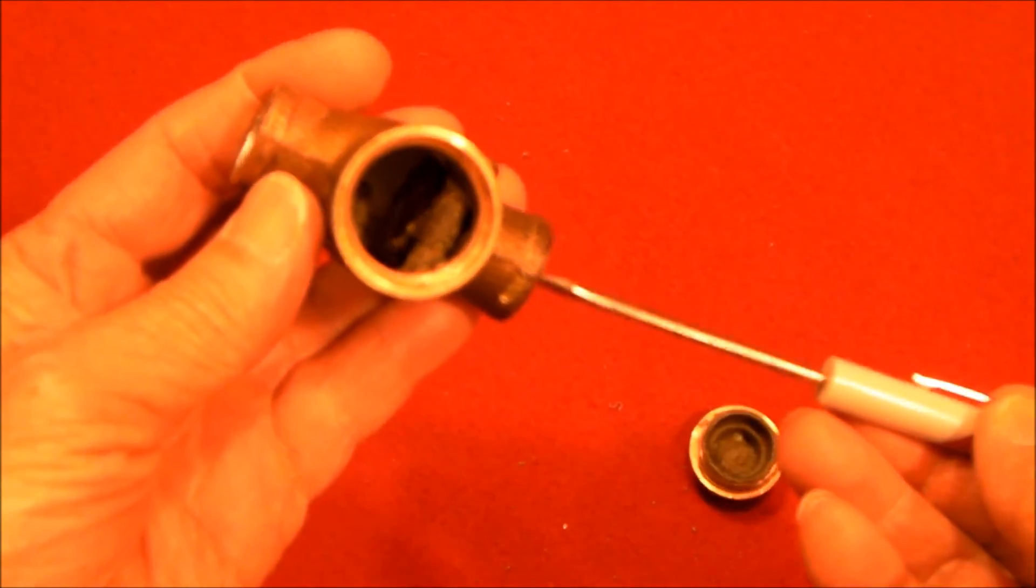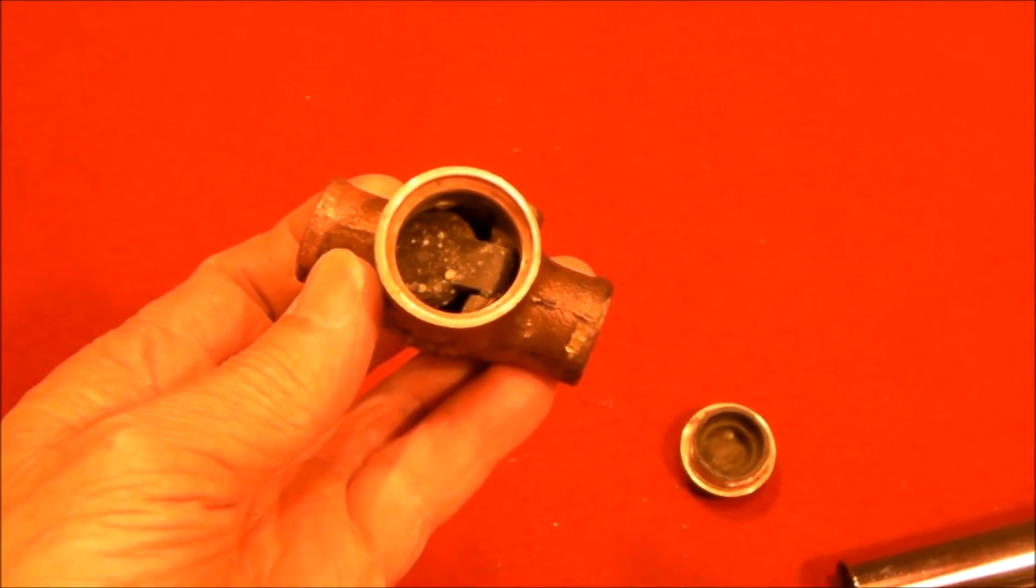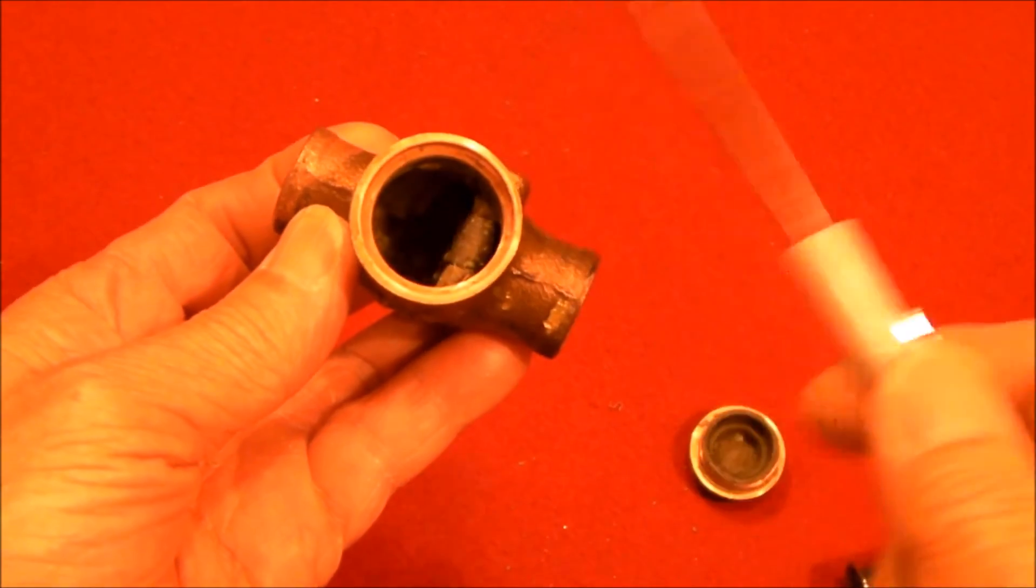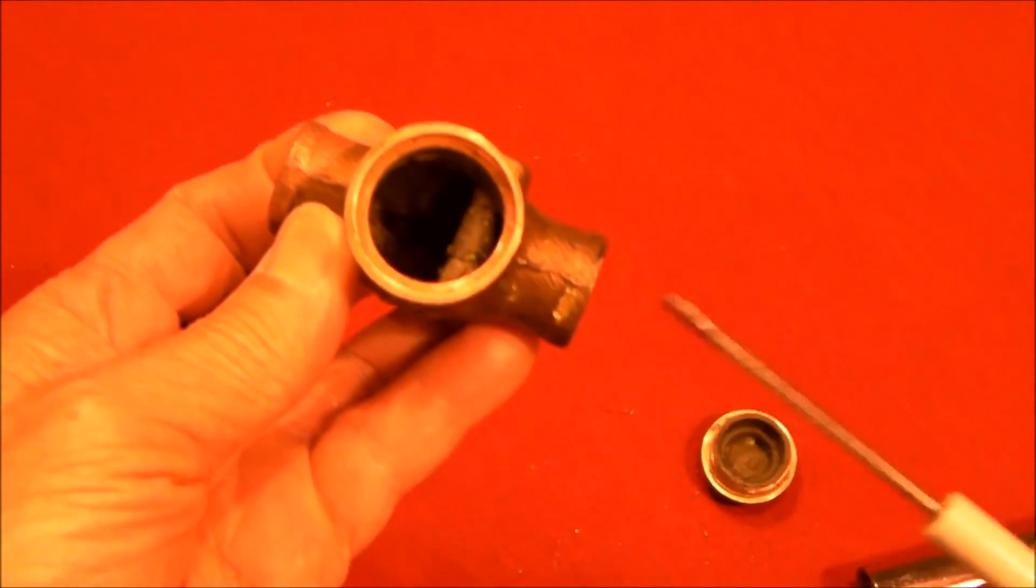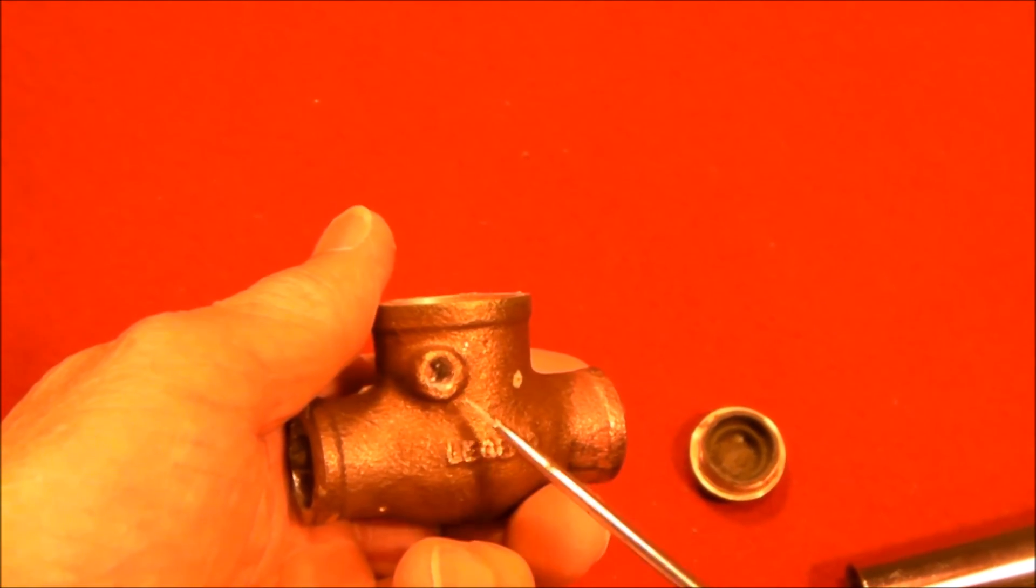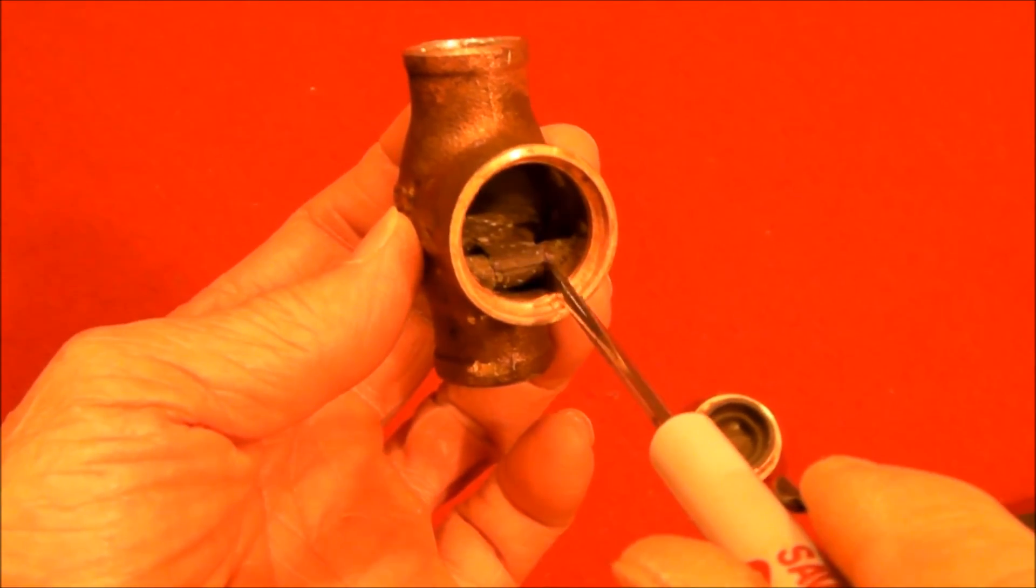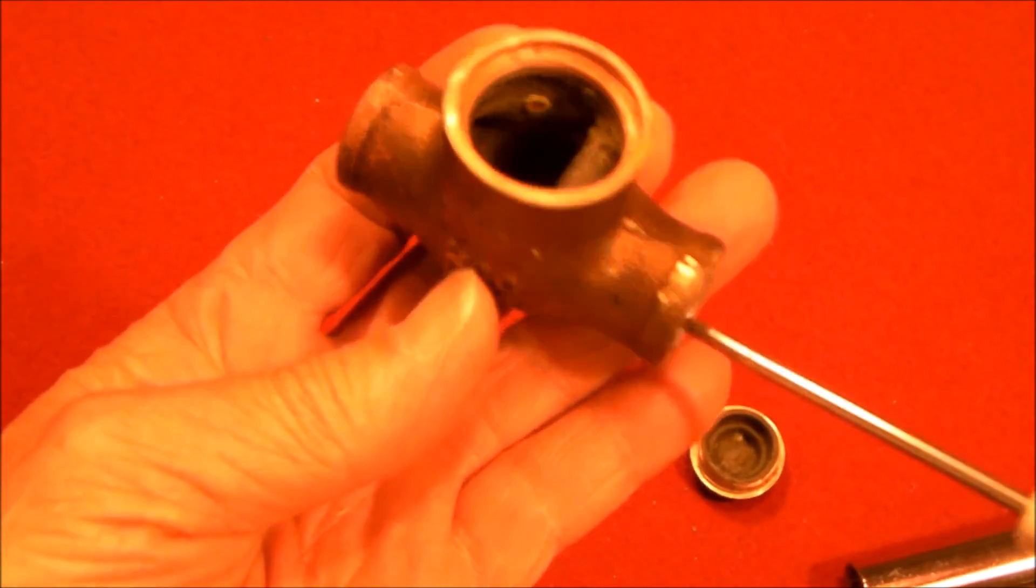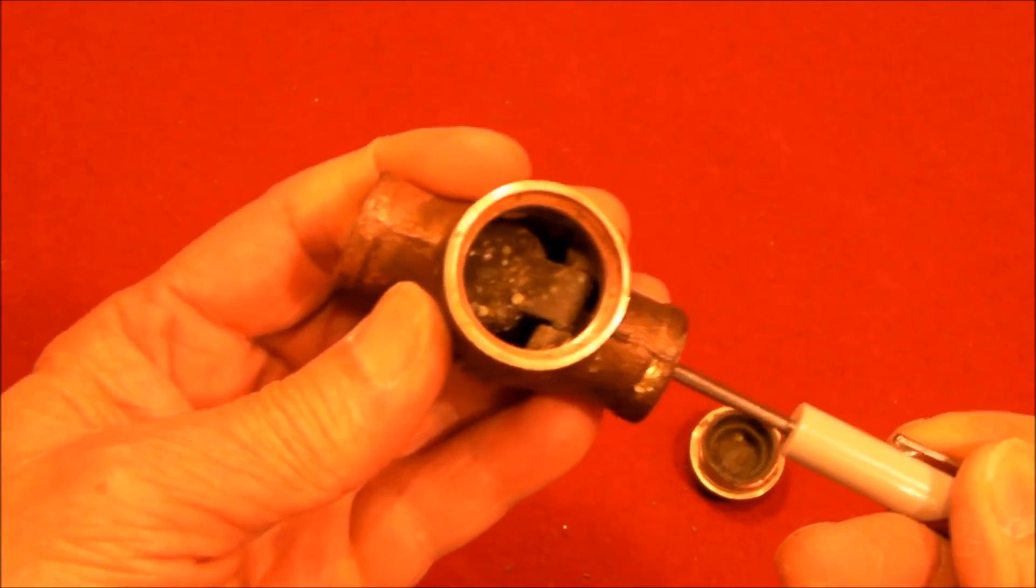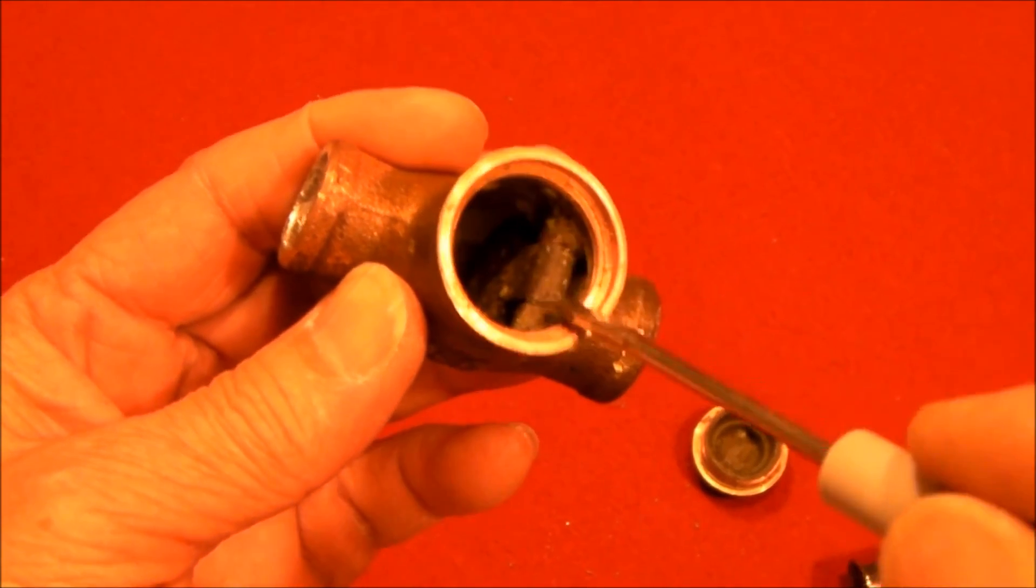And this is going to be very difficult to see, but there the gate is up and it's stuck up. I don't know whether a little bit of lubricant here would help. It appears to me that somewhere in this hinge area, here and here, this is where this thing is hanging up. There's an awful lot of corrosion on the inside. As I said, this is about a 16 year old check valve. Who knows how long it has been not operating correctly.